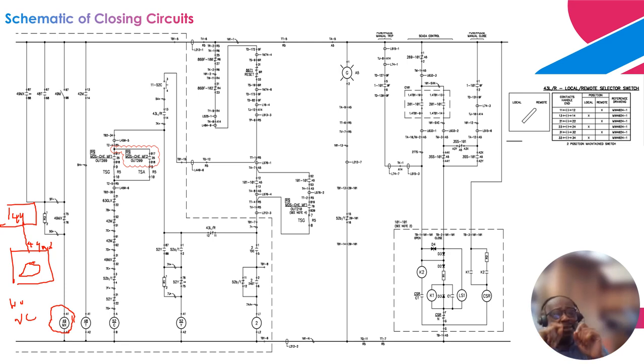And secondly, there is something called a wetting voltage, which is the voltage that goes through the contact. If the contact voltage that you need is different from the contact voltage in this relay, then you need an auxiliary relay to integrate with it to achieve the required voltage. Let's say you need a 24 volts wetting voltage, and this relay has contacts that are 12 volts or 48 volts. You cannot use that contact for your purpose. You need 24 volts, so you need to integrate another auxiliary relay, and that is what this 49 mx is.